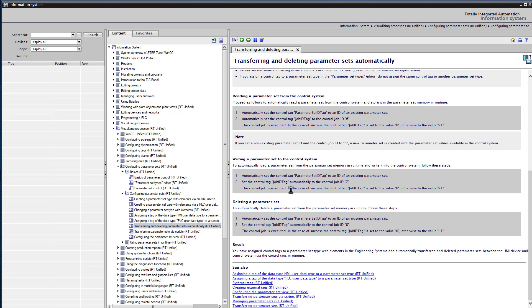If you want to download to the PLC from TIA Portal, then you use job ID of 7. And again, you just put in the ID of the parameter set that you want to download into the process. And for both of these operations, the job ID tag is going to change value. And if it goes to 0, then that means it was successful.